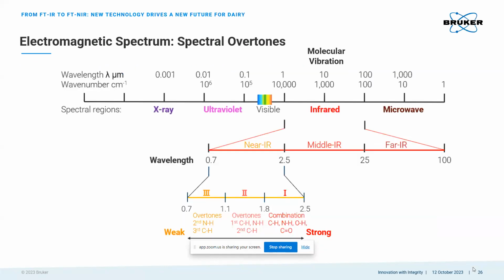Now, when we talk about FT-IR instruments, we are usually referring to those instruments that use the mid-IR region of the electromagnetic spectrum. That's between 4,000 and 400 wave numbers, where NIR instruments use the region from about 12,000 to 4,000 wave numbers. Beyond that, another key difference between mid-IR or IR and NIR is that mid-IR is characterized by strongly absorbing fundamental vibrational transitions, where NIR is characterized by overlapping overtones and combination bands. So what does this actually mean?